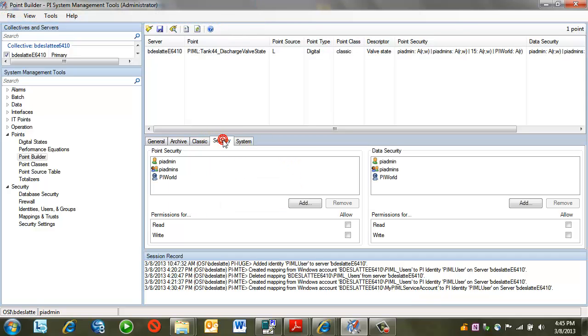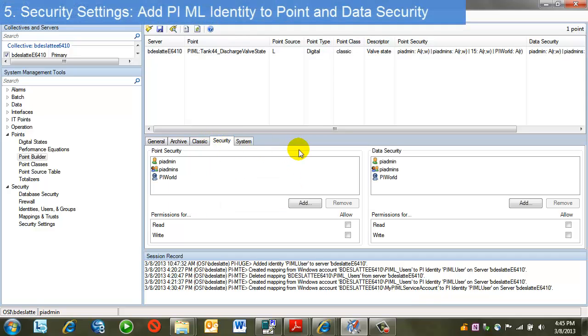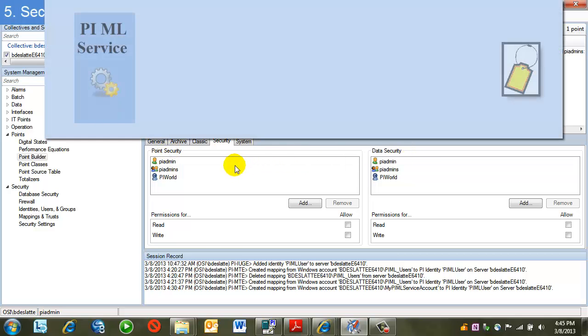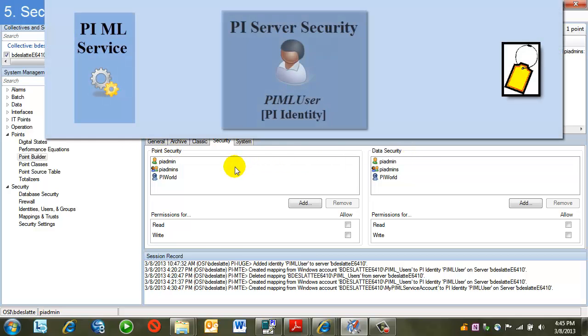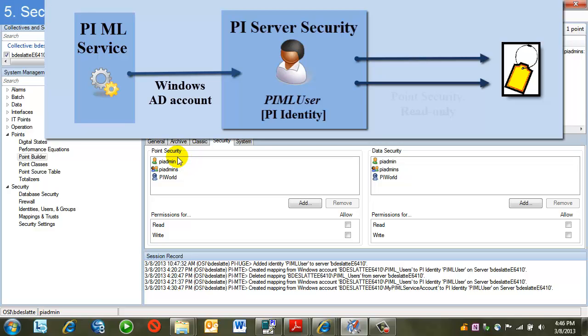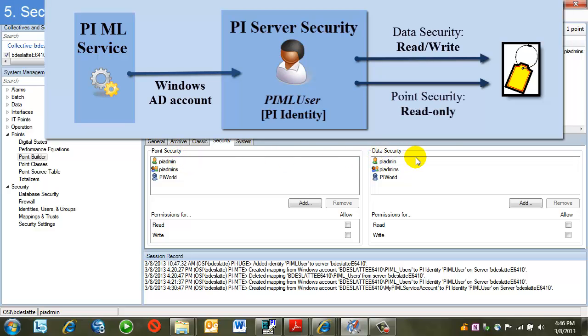I'll come over to the security tab. I see that I have the default point and data security. What I need to do is add my identity for both point security and data security. PI ML users need read access on point security and read write on data security so that they can write to the tags.